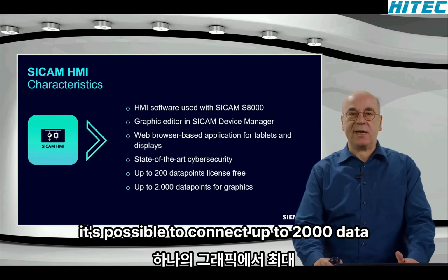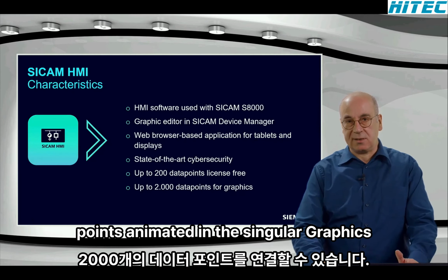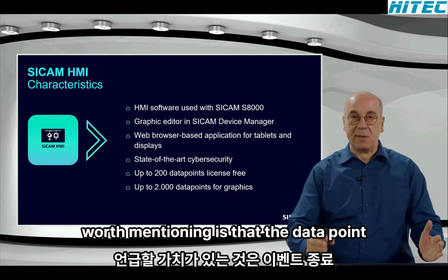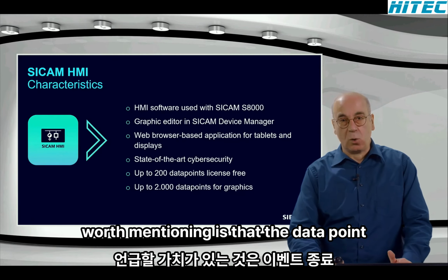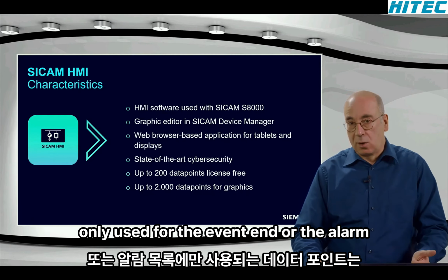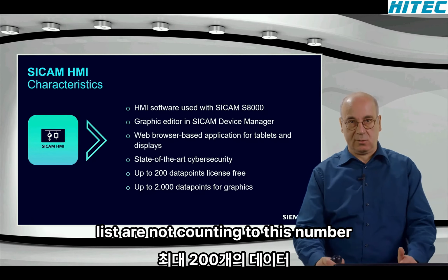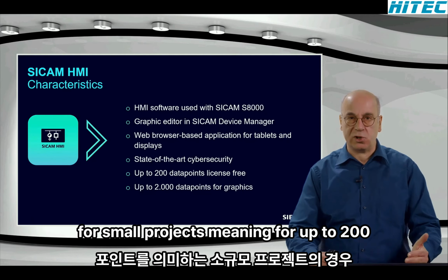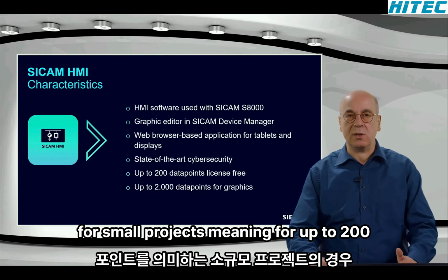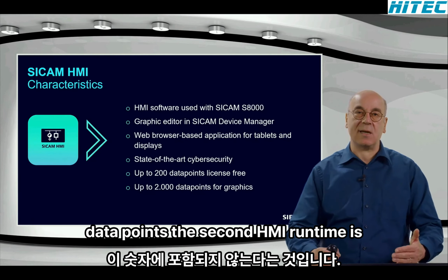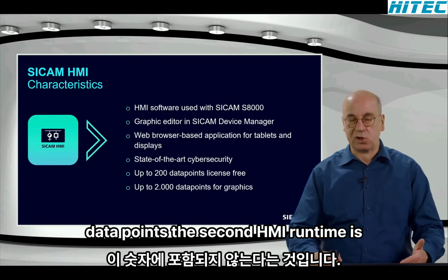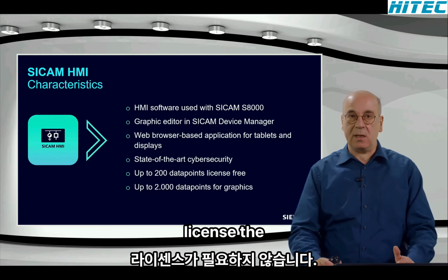It's possible to connect up to 2,000 data points animated in the single-line graphics. Worth mentioning is that the data points only used for the event and or the alarm list are not counted in this number. For small projects, meaning for up to 200 data points, the Sicam Hmi runtime is free of charge and doesn't need a license.